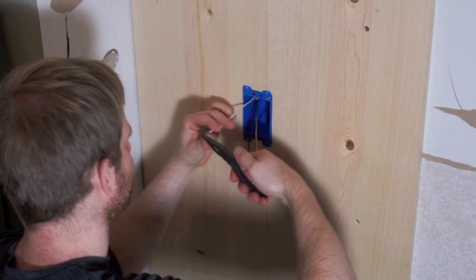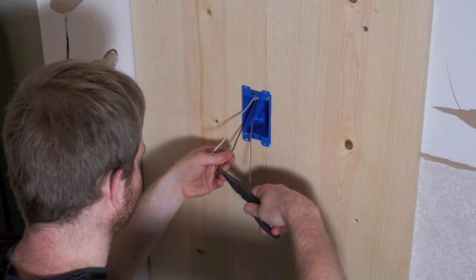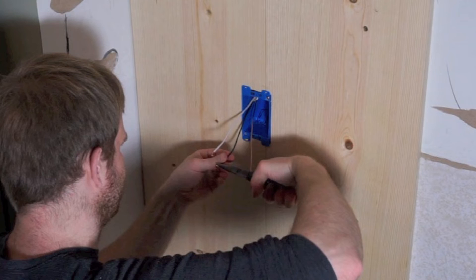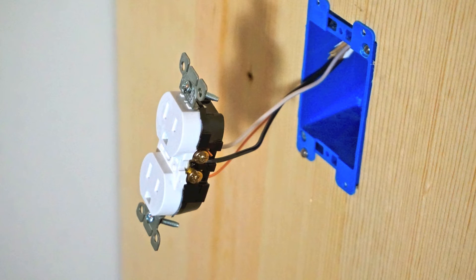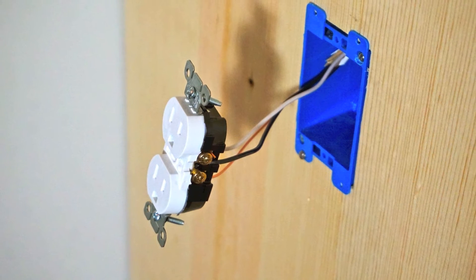Make sure you loop the wire in the same direction as the terminal screw tightens, so that the wire doesn't get pushed out as you tighten the screw down. The white wire, if it is in fact neutral, should be connected to the neutral terminal on the outlet, which is oftentimes a silver or gray screw. The ground will be attached to the ground terminal, usually green, and the black wire, assuming it's hot, should be connected to the hot terminal, which is usually brass colored.